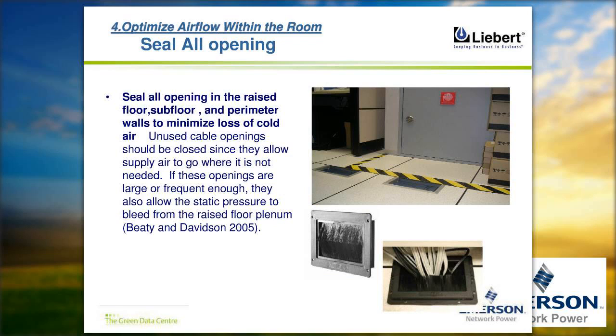Then, as I mentioned, there are a lot of airflow openings under the tile or nearby racks that need to be sealed up properly. Even cable entry points to the rack need to be blocked through a KoldLok system. There are a lot of new techniques available in the market today, either grommets or brushes, that can be used for blocking the air or mixing of the air.